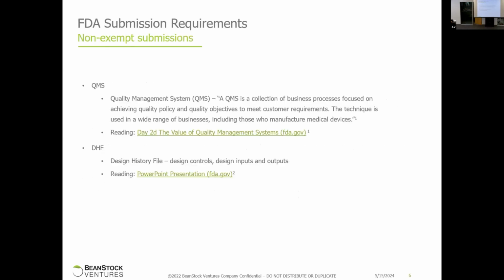So, at a high level, your FDA submission requirements. Once you determine that you're a medical device manufacturer, which I'll explain in a little bit, there are two areas you need to implement, in terms of your company, in terms of process and your product, right? So you need to implement a quality management system. ISO 13485 is highly recognized. That covers your processes, tools, and procedures, et cetera, that provide your design controls for the development of your product. The design history file is primarily what's going to be in your FDA submission. Your design history file is all of the technical specifications of your product: your specs, your architecture, your design, all of your testing, et cetera. These are the two main elements that should be in place as a medical device manufacturer.